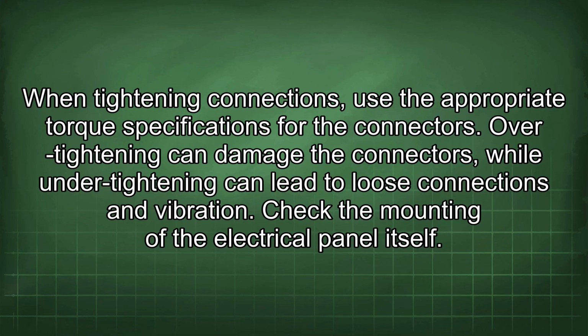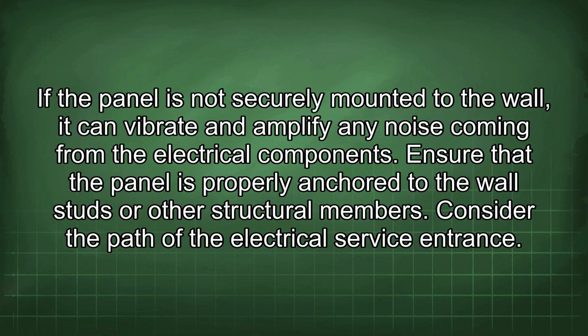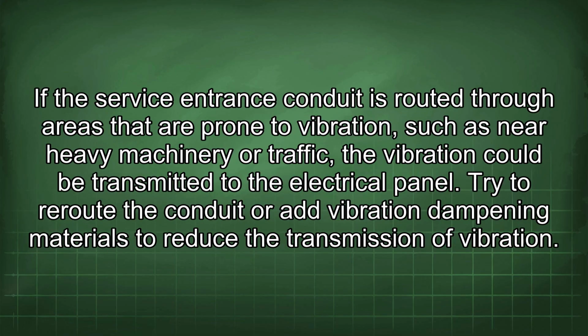Check the mounting of the electrical panel itself. If the panel is not securely mounted to the wall, it can vibrate and amplify any noise coming from the electrical components. Ensure that the panel is properly anchored to the wall studs or other structural members. Consider the path of the electrical service entrance. If the service entrance conduit is routed through areas that are prone to vibration, such as near heavy machinery or traffic, the vibration could be transmitted to the electrical panel. Try to reroute the conduit or add vibration dampening materials to reduce the transmission of vibration.